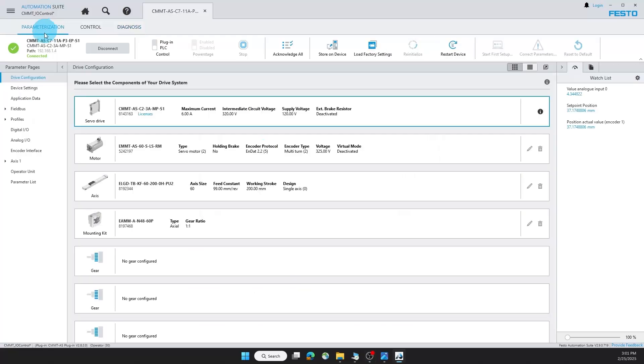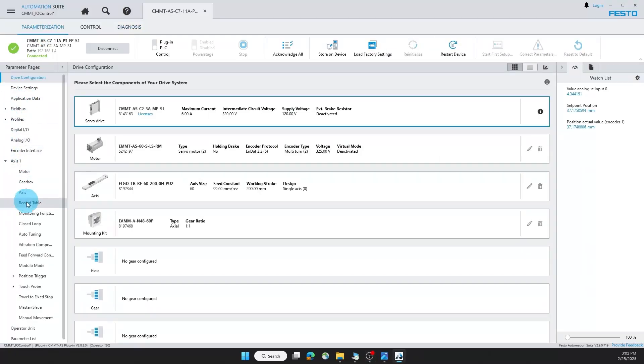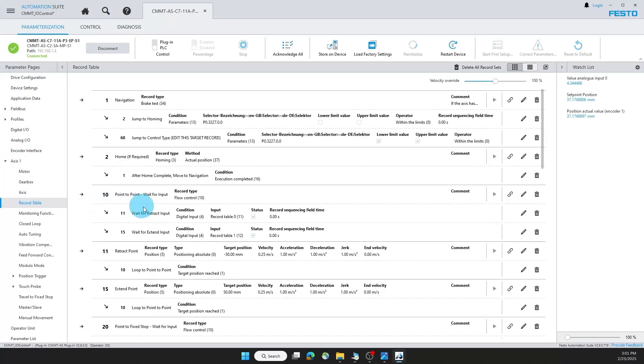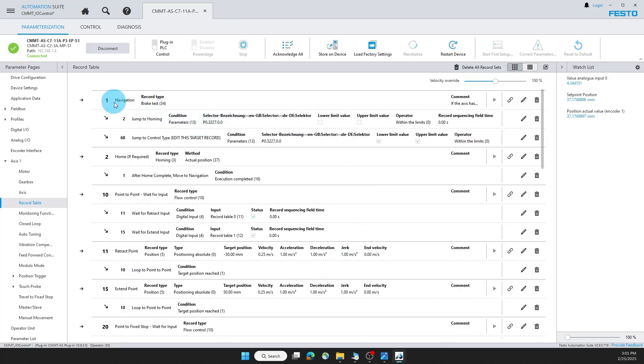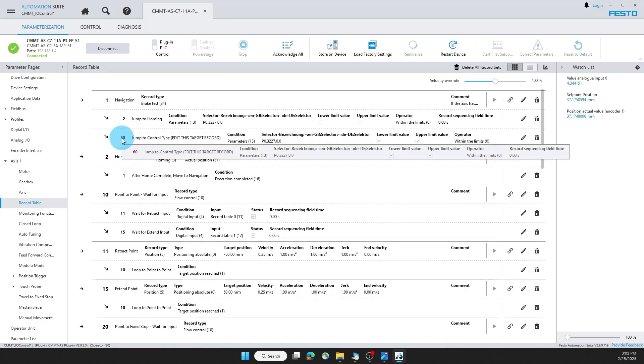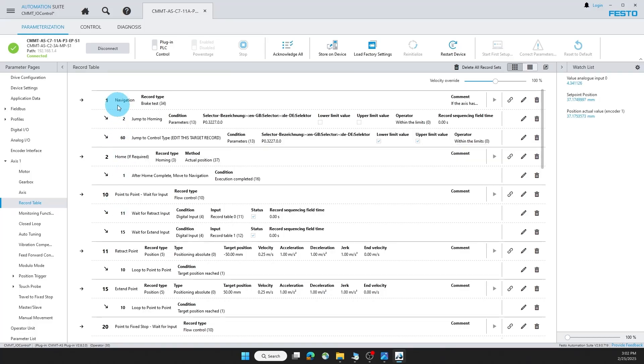From parameterization, go under Axis 1, record table. And this will show you the exact flow of how I.O. control works. Starting with record one, where it navigates based on the status of the homing value. If your homing is valid, then it will move directly to your control type that you desire. In this case right now it's set up at 60. If your homing is not valid, then it's going to step to record two, which is going to automatically home your motor.